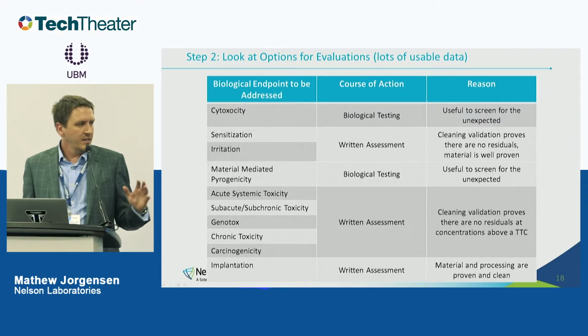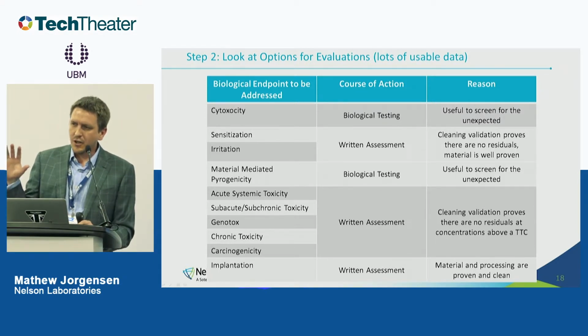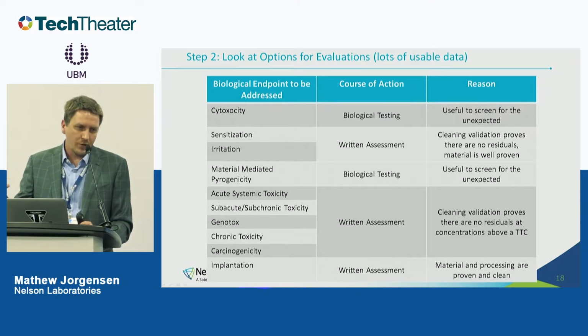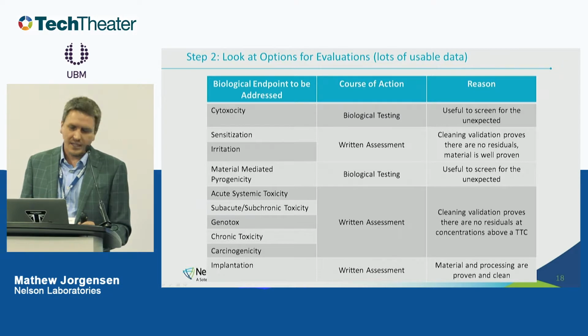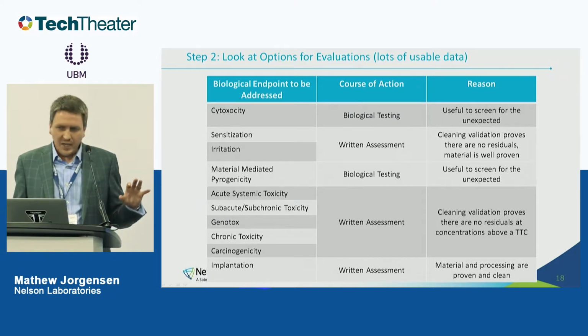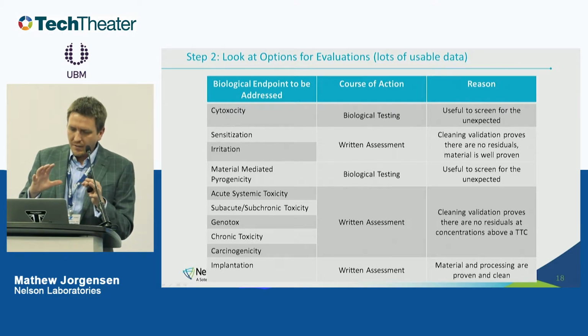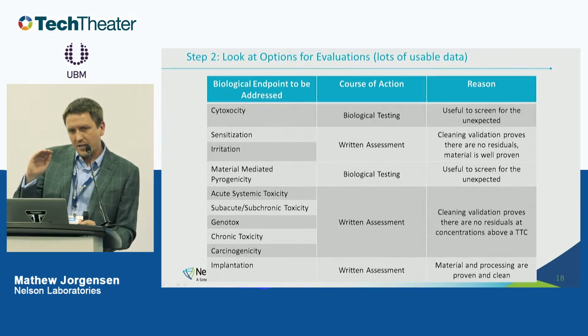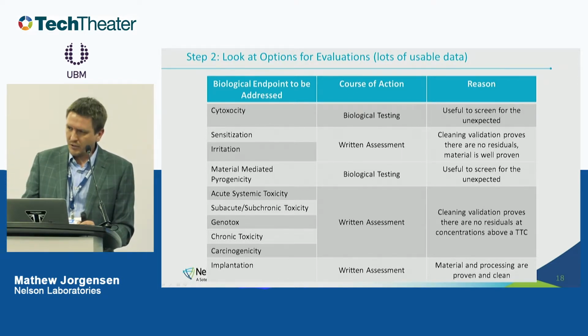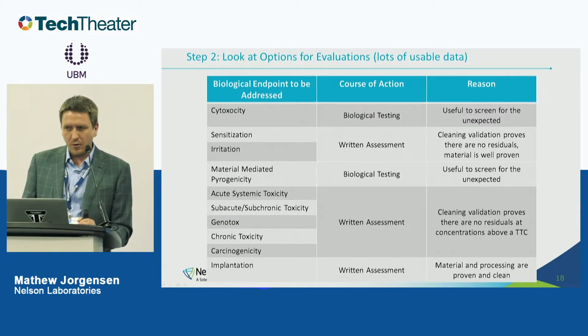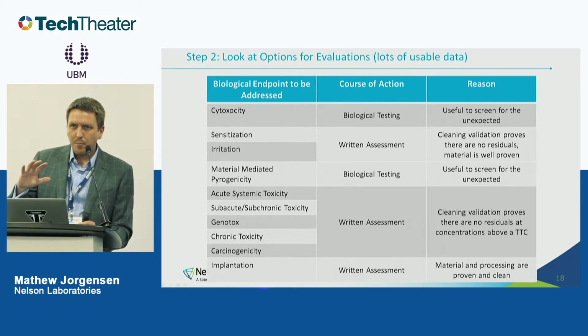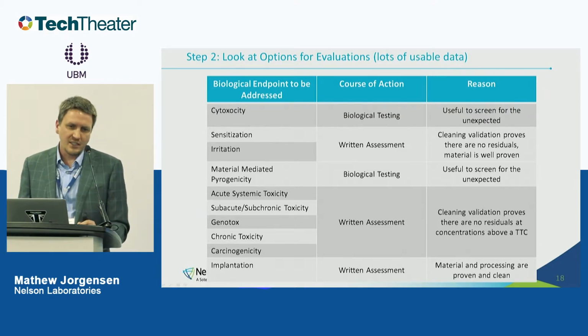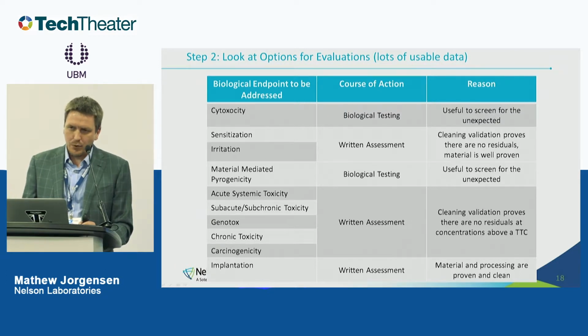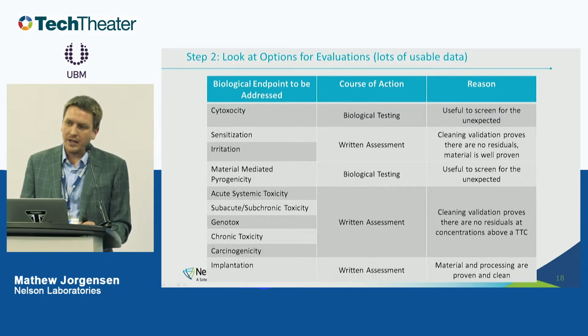Now, the case that I'm showing here is a little bit special because I chose an orthopedic implant device that's made out of a well-known, well-characterized material like CP titanium or stainless steel. Because with those materials, we know the composition of the material very, very well. And if the implant's finished according to a certain ASTM specification, we also know what the surface is like. And under those conditions, we can really say a whole lot without testing, so long as the supplier or the manufacturer can really prove that the device is free of manufacturing residuals. So it's a good plug for a cleaning validation. If you can really prove that your device is clean and you have a device made from a really well-known material, then that can help you a whole lot in avoiding unnecessary testing.